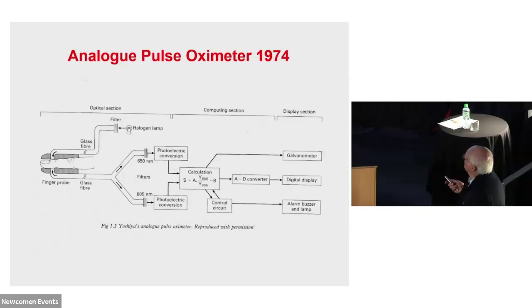But it did to a certain extent, because it was looking at two different wavelengths, which were then converted to a ratio between the two, with an A to D converter, a digital display, a galvanometer and alarms. And it would actually, for reasons we'll see, measure the level of haemoglobin saturation in the arteries and not just through the skin and the finger. But it tended to burn the finger, which was a great shame.